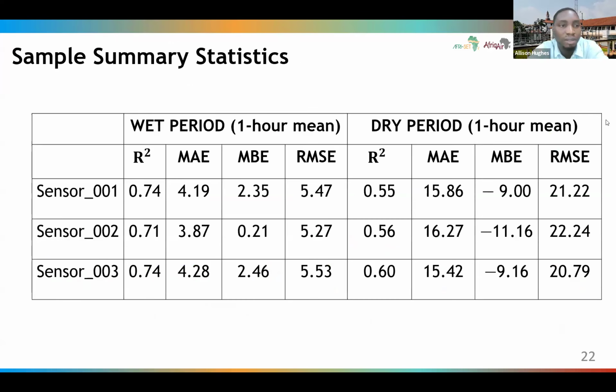These are some of the metrics in our reports: the R-squared and error measurements like MAE and MBE, which tell whether sensors are overestimating or underestimating compared to the reference monitor, shown as positive or negative MBEs. After evaluation, you then look at how to calibrate the sensors, since they usually don't perform as expected during the dry season.